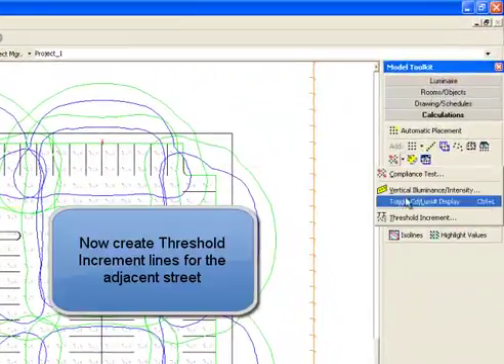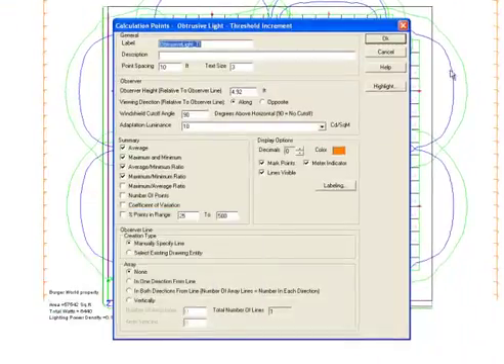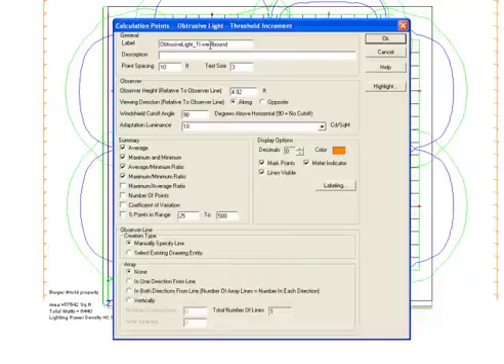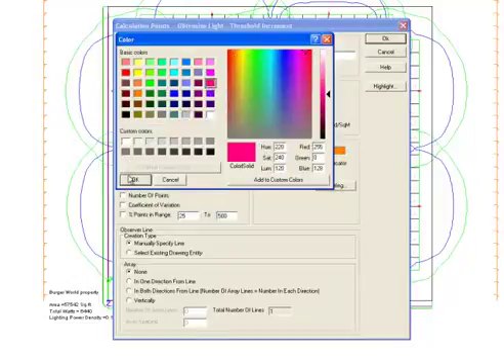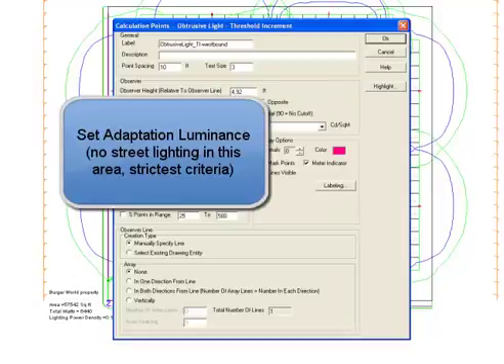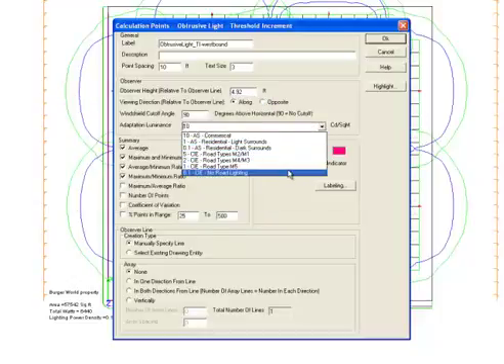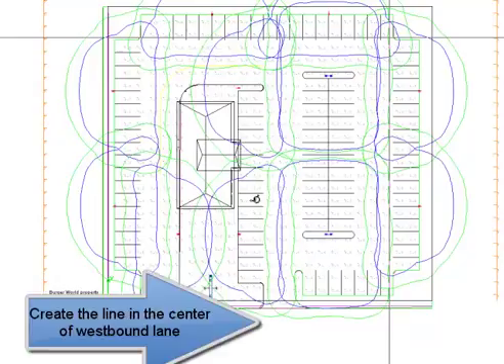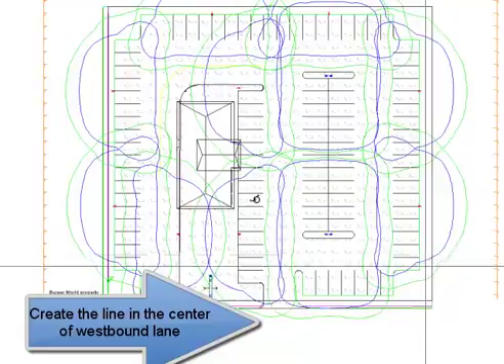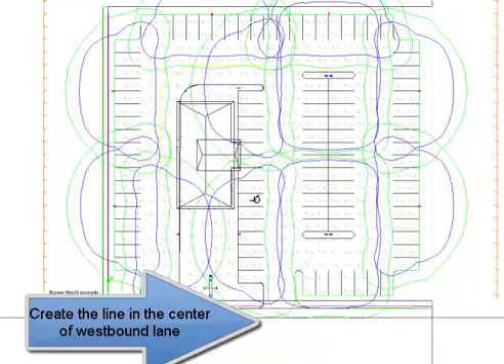Now create threshold increment lines for adjacent street. First for the westbound lane. Change the label to westbound. We'll change the point color. And finally we'll set the adaptation luminance for no street lighting in this area. This is the strictest criteria. Create the line in the center of the westbound lane.